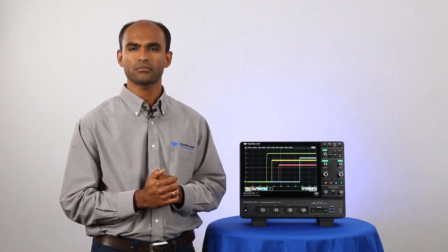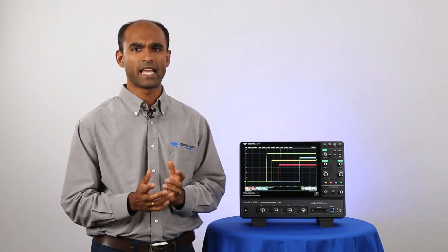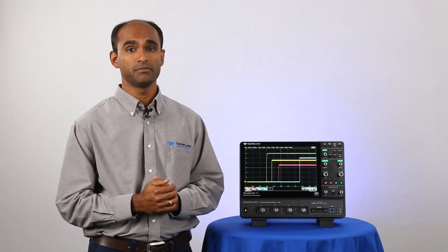Can I use them to measure a small voltage across a series or shunt resistor? We have a probe that has 10 times the gain, lower noise, and higher CMRR. What is the CMRR? It's 80 dB. Wow.